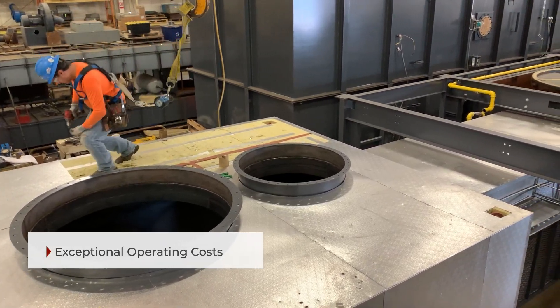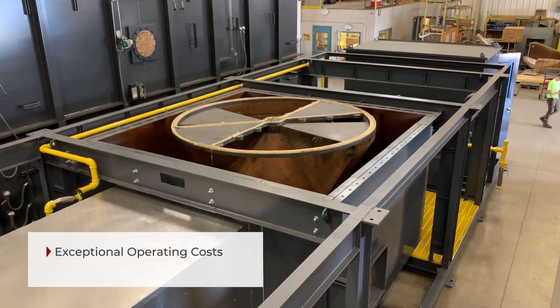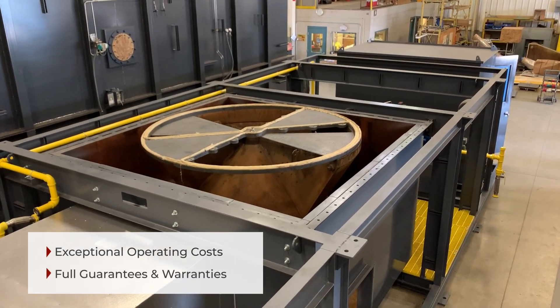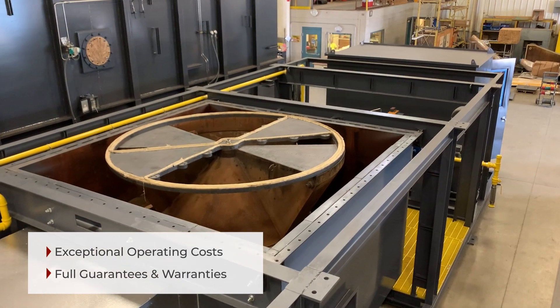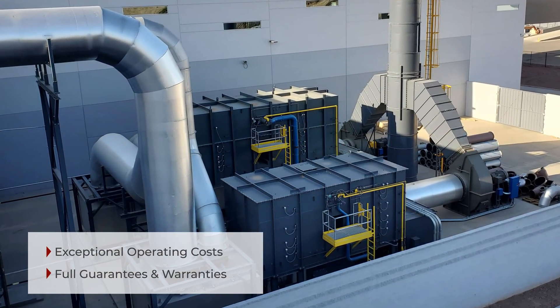This application has both cold and hot air streams that combine just prior to the RTO, so an inlet mixing box was added before the two RTOs to control temperatures entering the RTO, preventing condensate buildup on duct walls and the RTO valve.